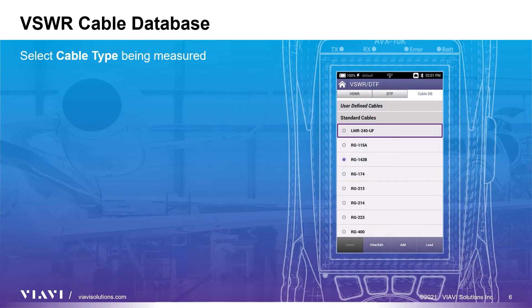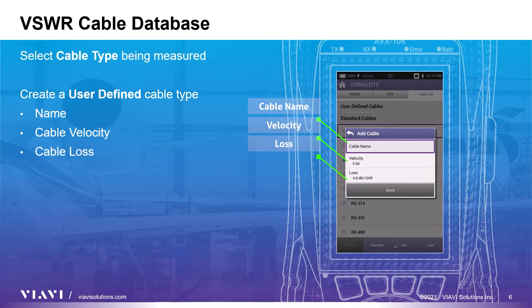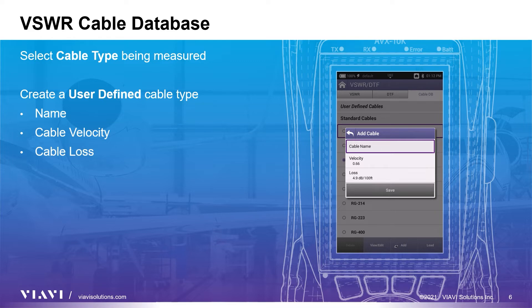Now let's move to the selection of the cable type that you are measuring. Click on the cable DB tab and choose the cable being tested from the provided list. If your specific cable is not provided, you can add a cable type by clicking the add button and entering a name, cable velocity, and cable loss as measured in dB per 100 feet. The cable velocity is usually between 0.6 and 0.9, or may be specified as a percentage between 60 and 90 percent. These values are specified by the cable manufacturer or can be researched on the internet if you know the cable type.